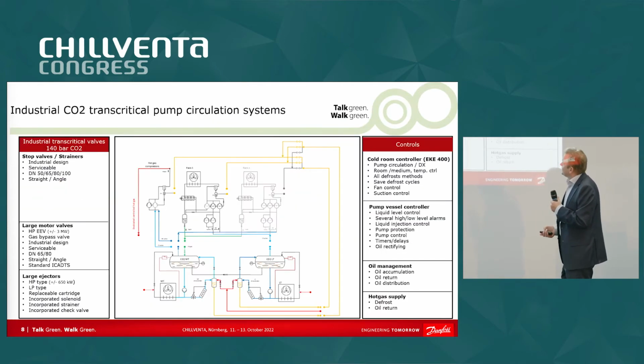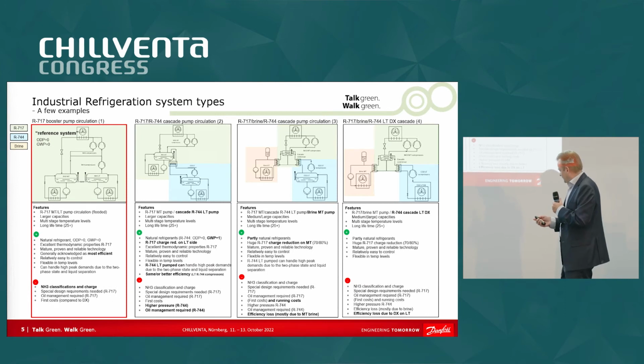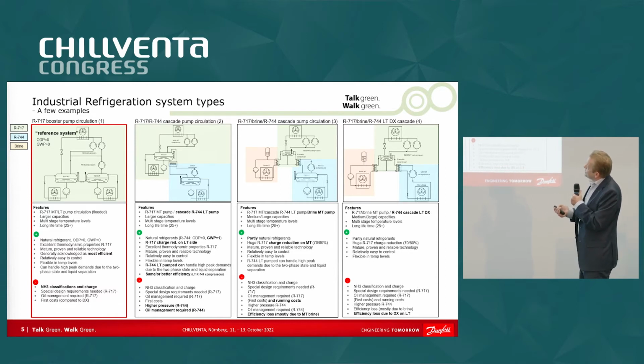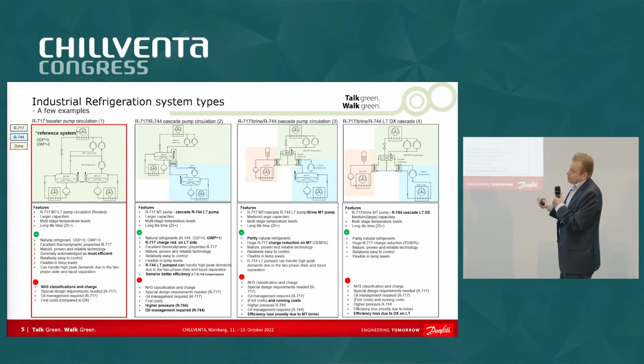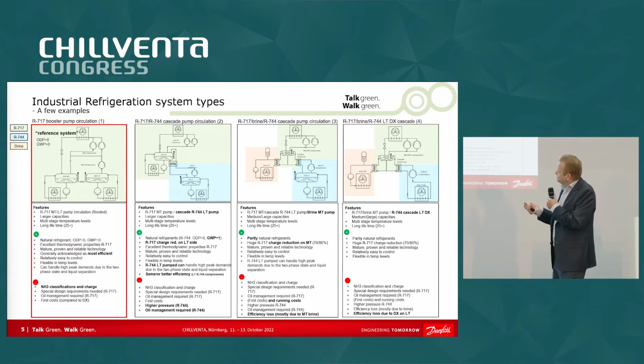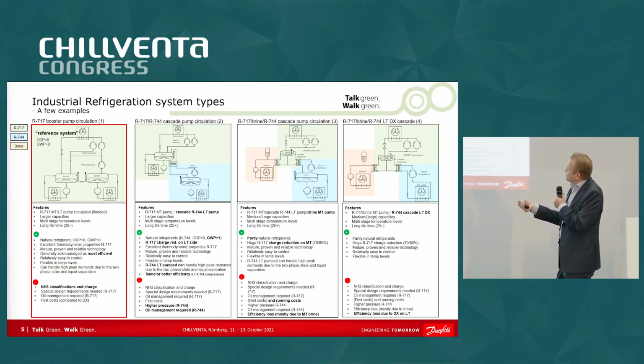The next system is basically the same. So we still have ammonia on the medium temperature charge, but we have a CO2 system below that. So here you reduce the whole low temperature system with ammonia charge. It's only CO2. The downside, of course, is you have CO2 as a refrigerant, but the pressures are much higher, so you have to be aware of that. And in this case, you also need to rectify the oil again, because in a flooded system, the oil remains at the end of the day in a separator. So how to get rid of it? So you need to rectify it. So the bold words in all these columns are the changes of the one before. Okay, so this is the first way of doing it.